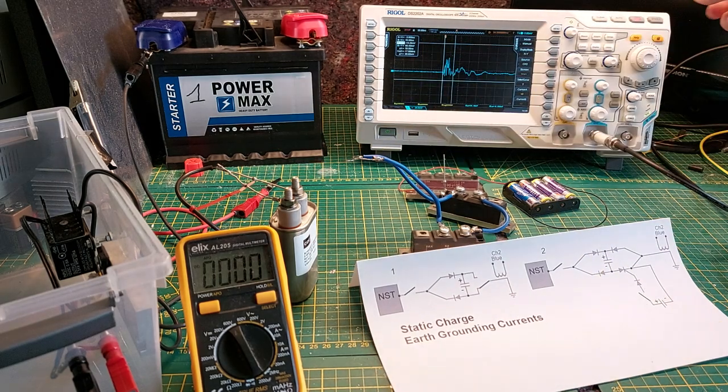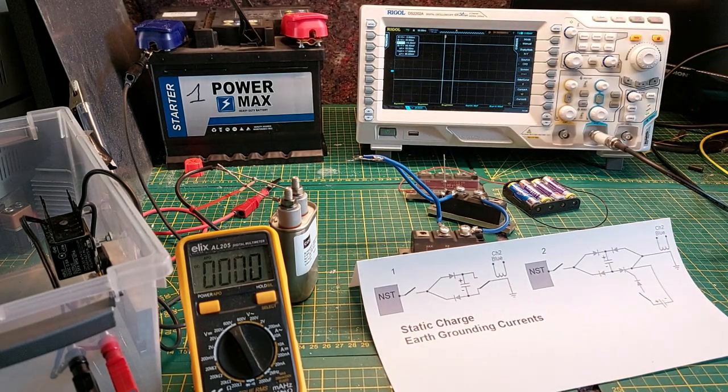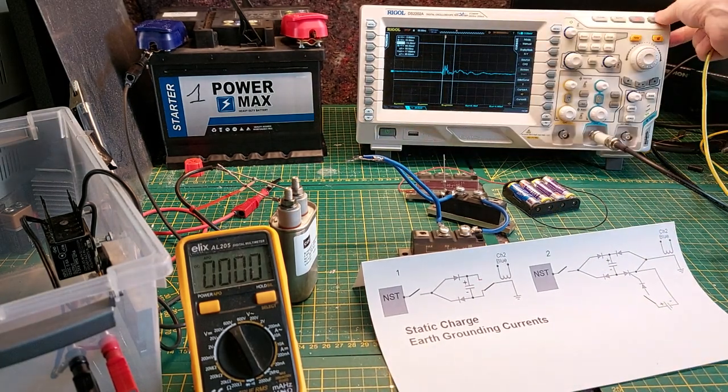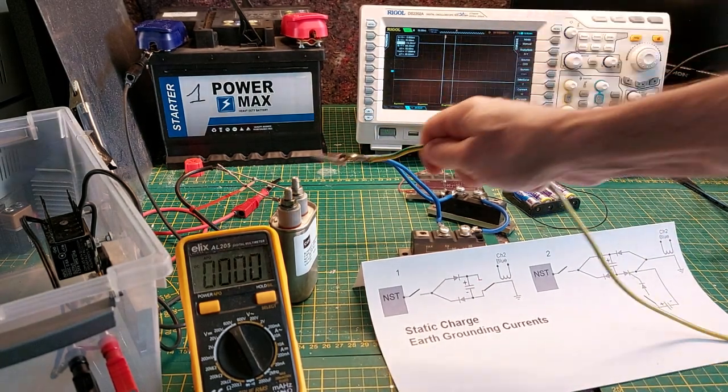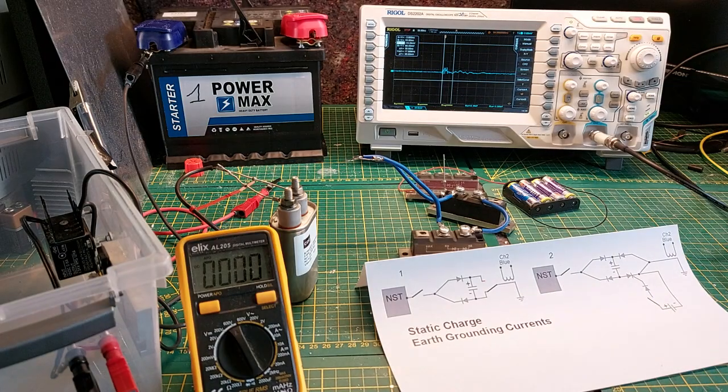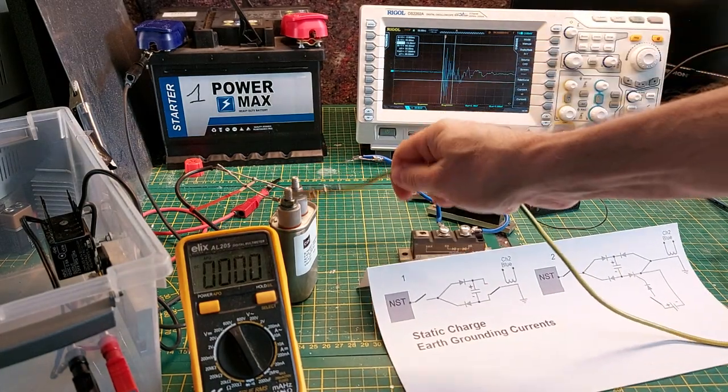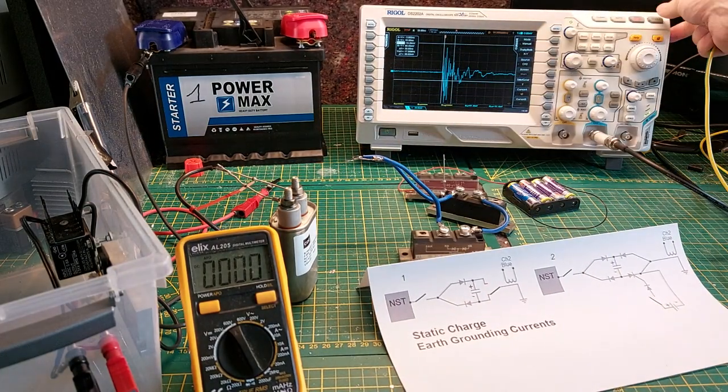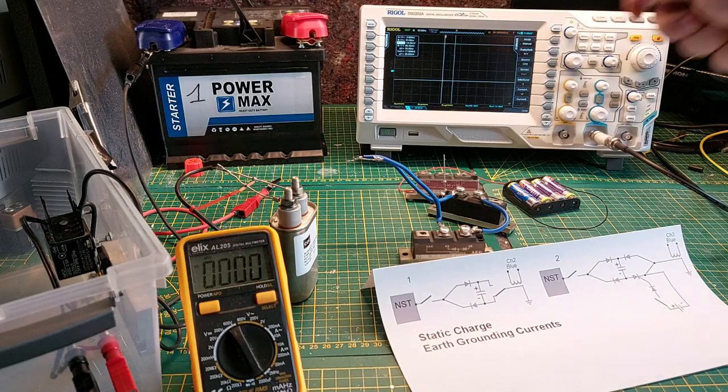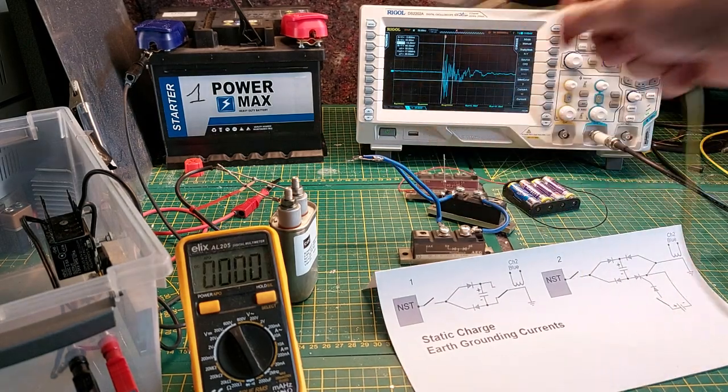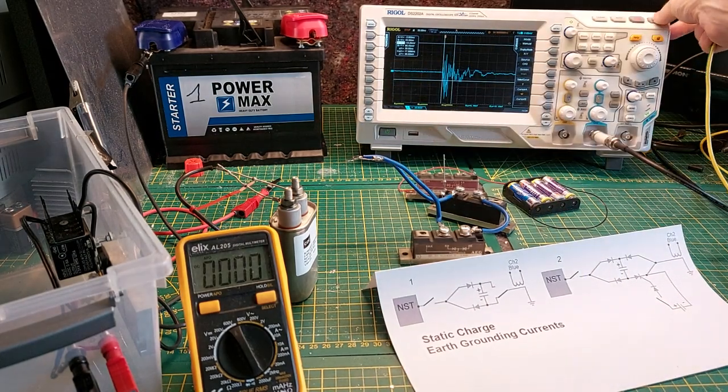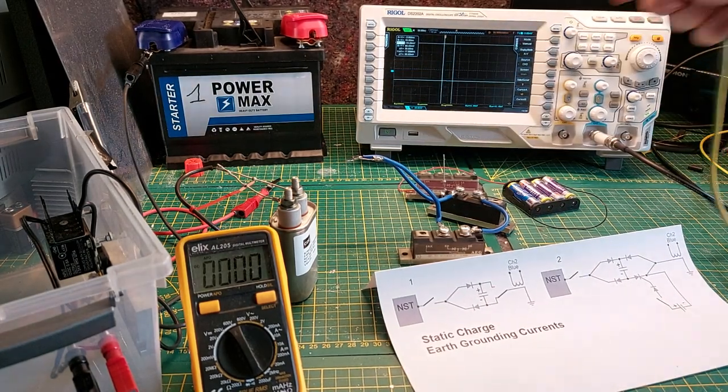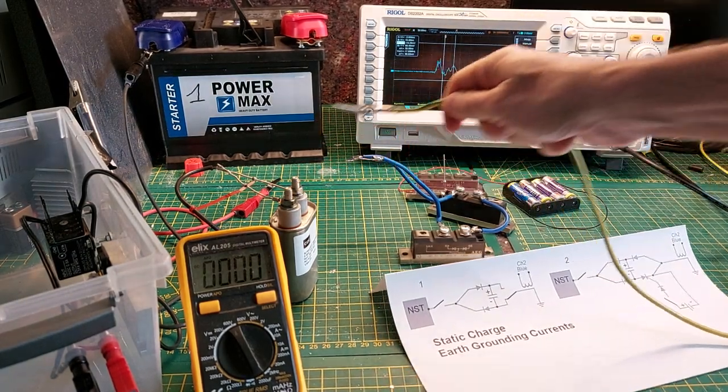Again, when I keep repeating you see that the value will go lower. So what I need to do is to change plate from plate to plate and then I get the most response out of the earth ground.